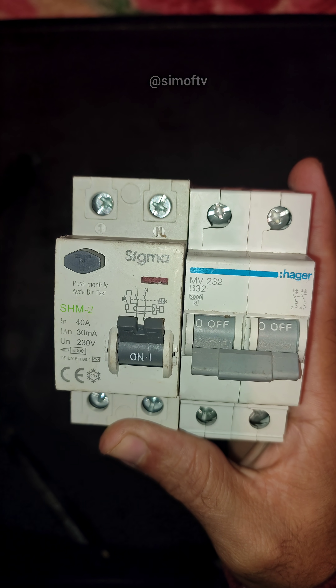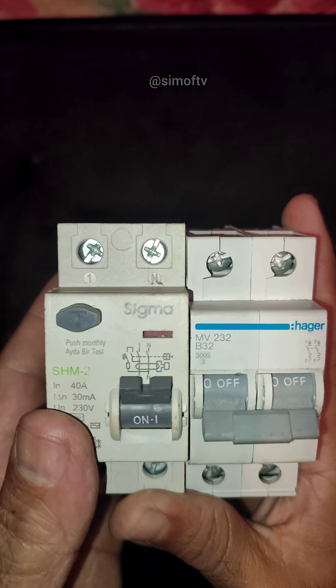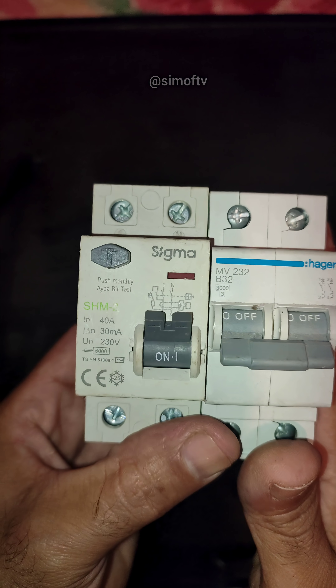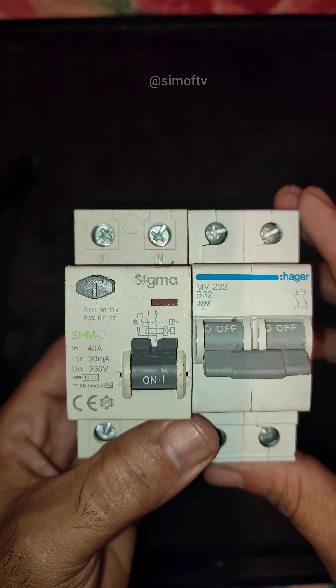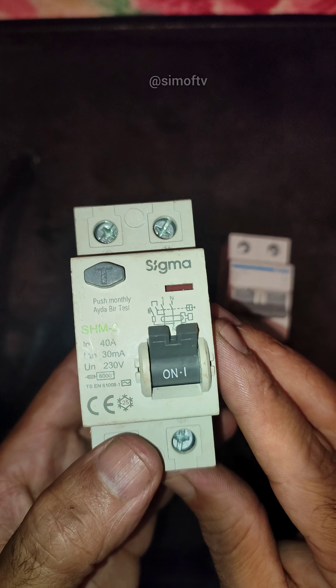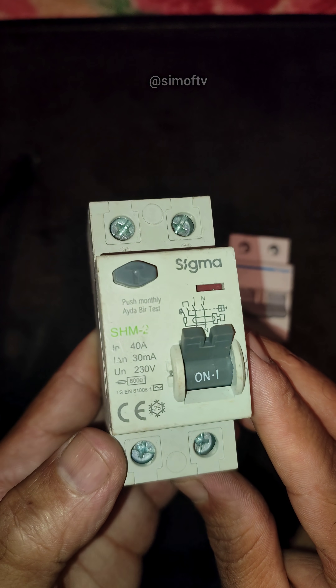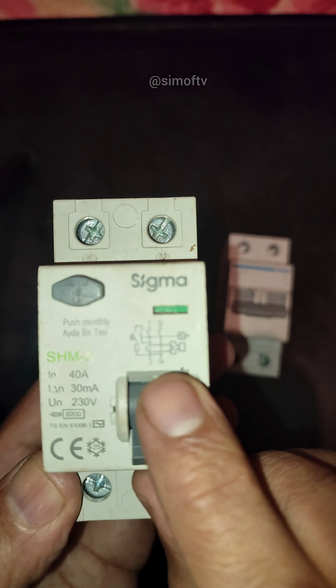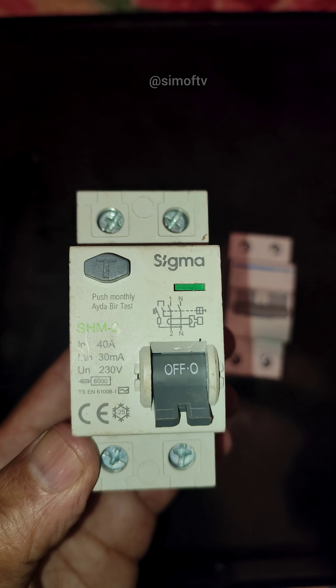Let's start with the device on the left, the Sigma SHM2. This is an RCD, also known as a residual current device. Its main purpose is protecting people from electric shock. It constantly checks the current going in and out of the circuit, and if it detects a leakage as small as 30 milliamps, it immediately cuts the power.